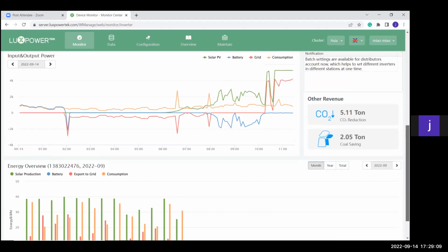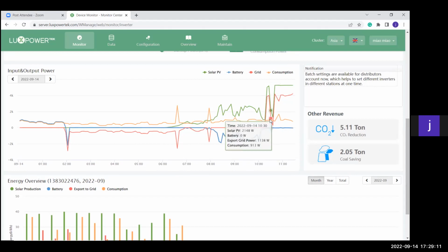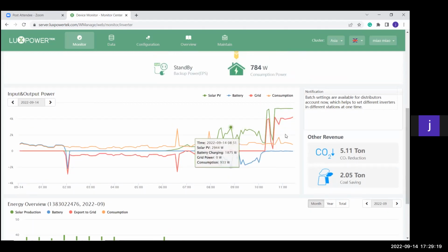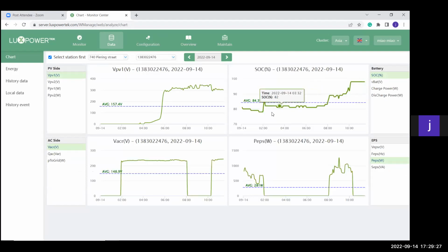So the grid will always be mimicked, and as you see here, he's pushing back to the grid, so that's why the grid is above the line and not at the bottom of that specific line again. Now my SOC, I can't have my SOC at this bottom graph here, but what we can do is if you go to data, then you can have the SOC of the battery displayed at this instance here.